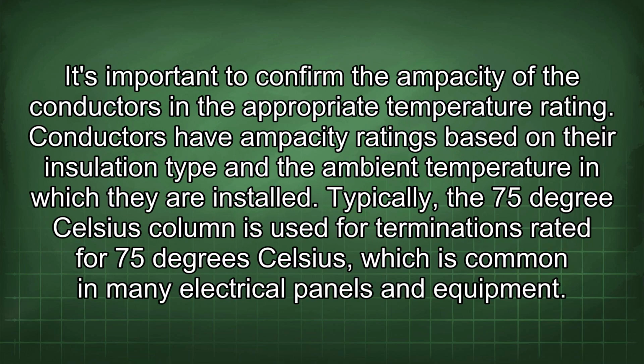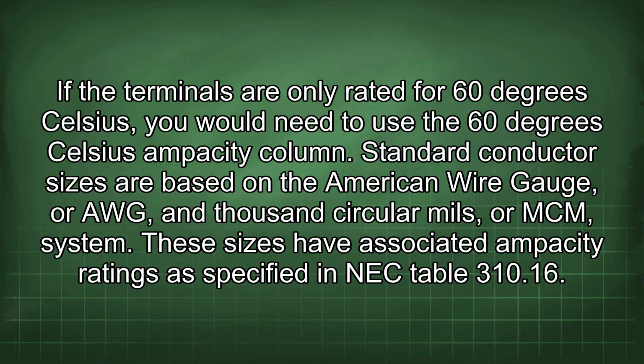It's important to confirm the ampacity of the conductors in the appropriate temperature rating. Conductors have ampacity ratings based on their insulation type and the ambient temperature in which they are installed. Typically, the 75 degrees Celsius column is used for terminations rated for 75 degrees Celsius, which is common in many electrical panels and equipment. If the terminals are only rated for 60 degrees Celsius, you would need to use the 60 degrees Celsius ampacity column.